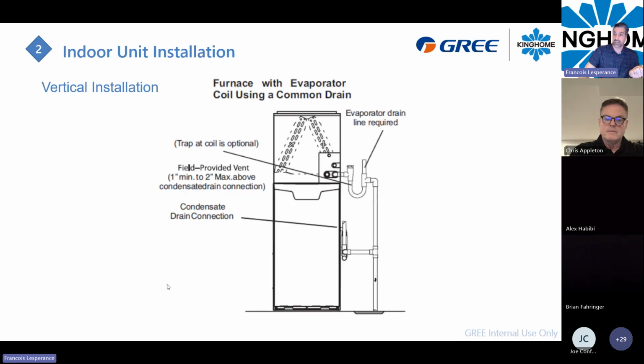But in the case that it's joined together right here, make sure to have a vent or something that reduces the air pressure here in the drain line, because otherwise it will create a problem with the flow switch or whatever in the furnace. So just make sure you have a small vent right here, and when the blower is on, you will not push excessive air pressure back to the furnace drain.